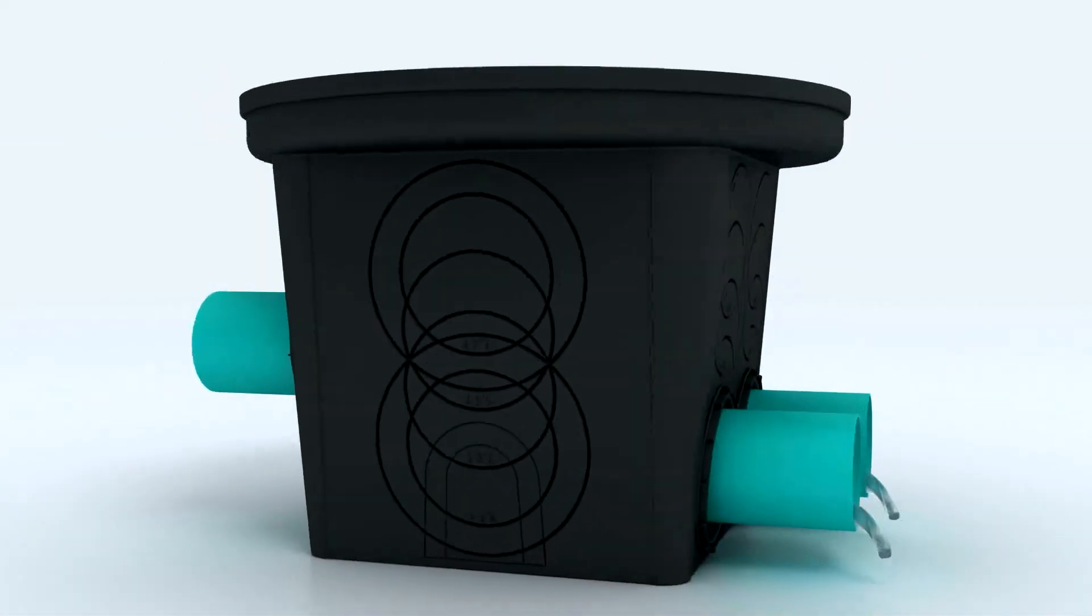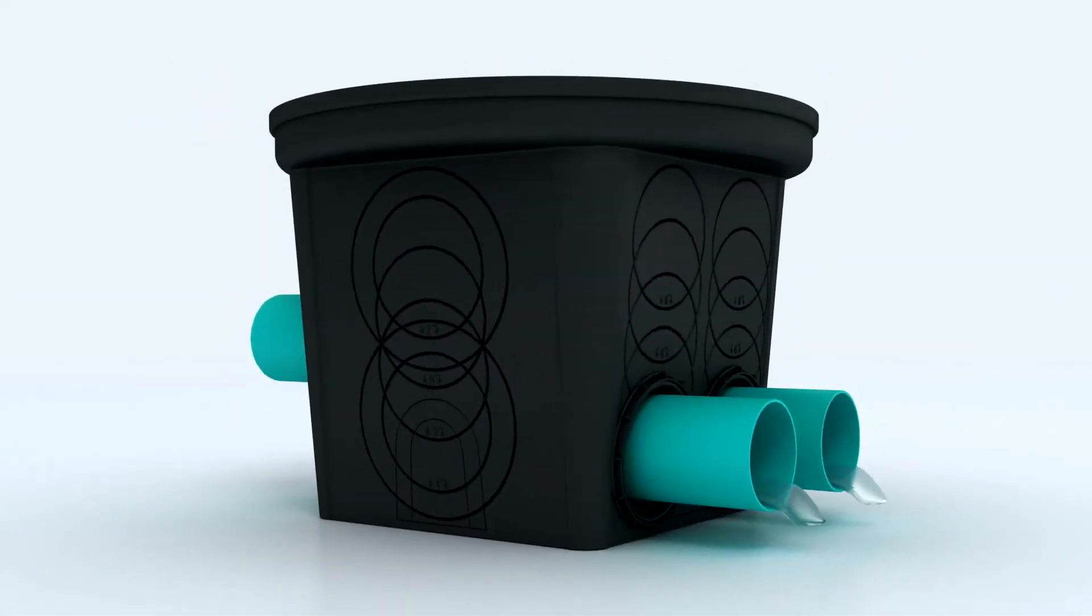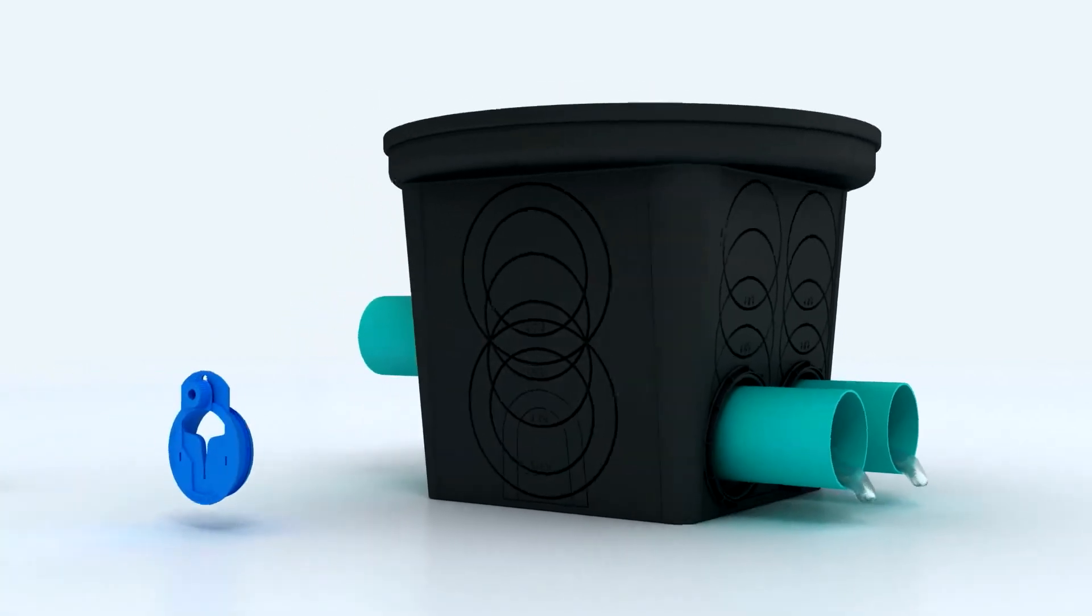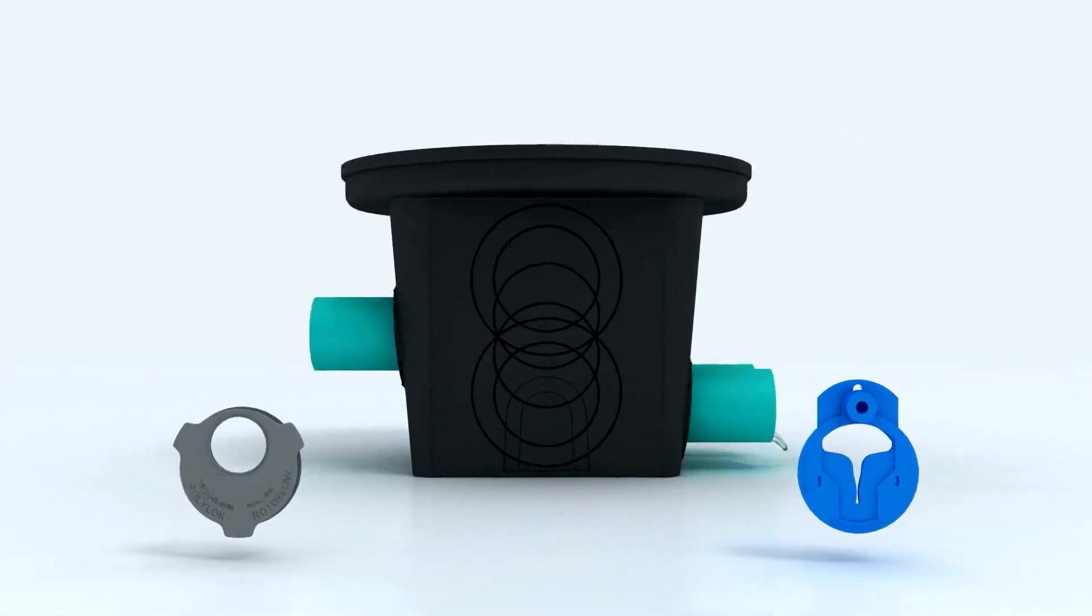To set the level on both the Equalizer and Rotoflow for even distribution, fill the bottom of the distribution box with water, then adjust all outlets to the same water level.